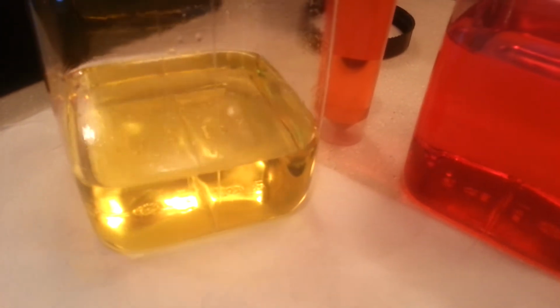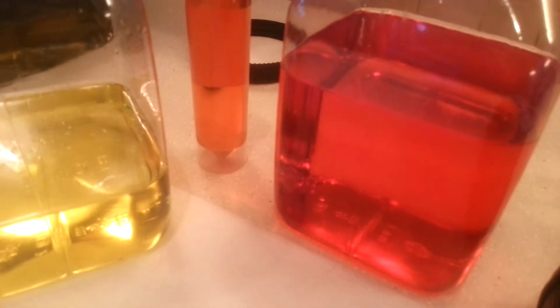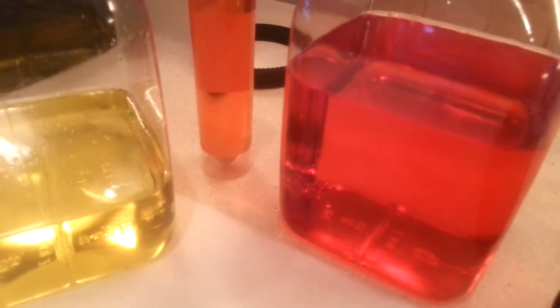So, as we all know, with the road diesel, the problem is that it's not used quickly, but it being hygroscopic, it absorbs moisture. Now, even though you've got 0.6% of bio in this, you will have the same impacts and the same effects of absorption of moisture to pollute and contaminate your fuel holding, unless you've requested absolute, as in no bio, which I think you're going to struggle at getting no minor percentage contents on from the refineries or your supplier in this day and age.